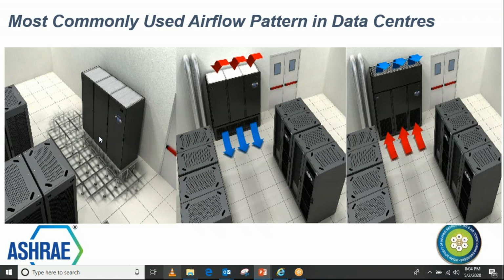Here are some of the airflow patterns, and what kinds of cooling units are available in precision air conditioning. These are mostly used, though many different types are also available. This is the cooling unit, these are the server racks, and this is the access floor. You can see the pedestals here. The unit has a fan below it, throwing cold air under the floor, and then, as you saw in the previous slide, cold air comes out in front of the racks and goes inside the racks, and the hot air comes back to the units from the top side. Okay, this is the bottom throw. This is called the bottom discharge type of cooling unit, which is typically used in most data center applications.